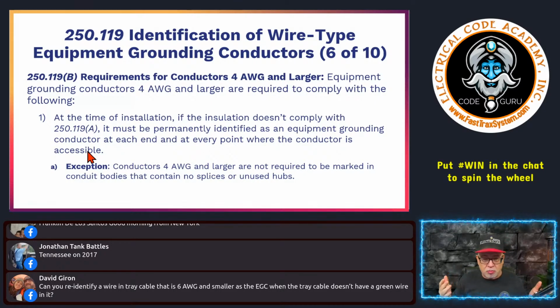Do we just assume that this green tape is going to magically start to come off and jump off of the conductor? No, some people are reading permanent so literally. Look, tape is acceptable, okay? You can color it, you can paint it, as long as the paint's not detrimental to the insulation, okay? More like a water-based paint or something that's not going to cause a reaction, that type of scenario, okay?